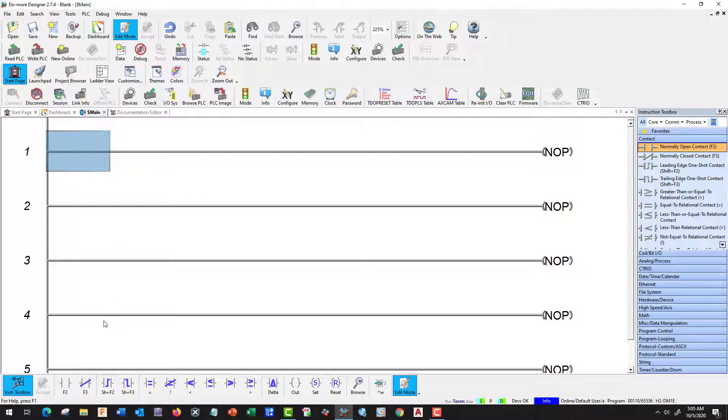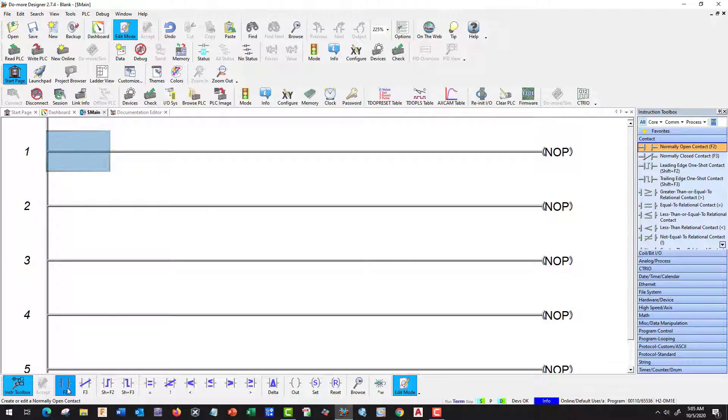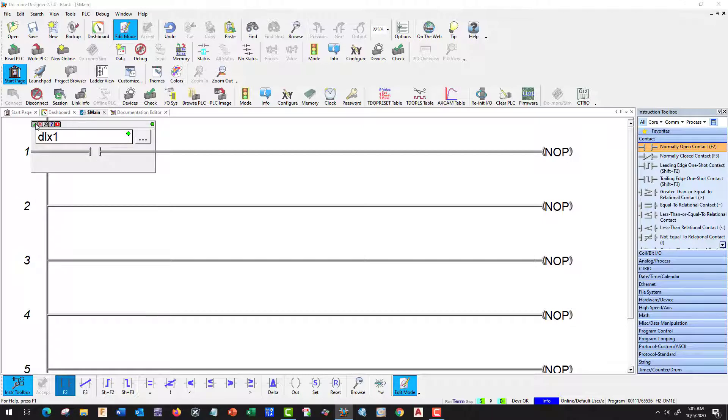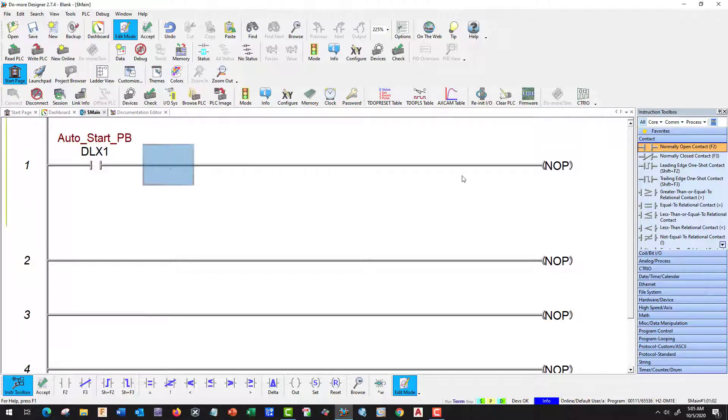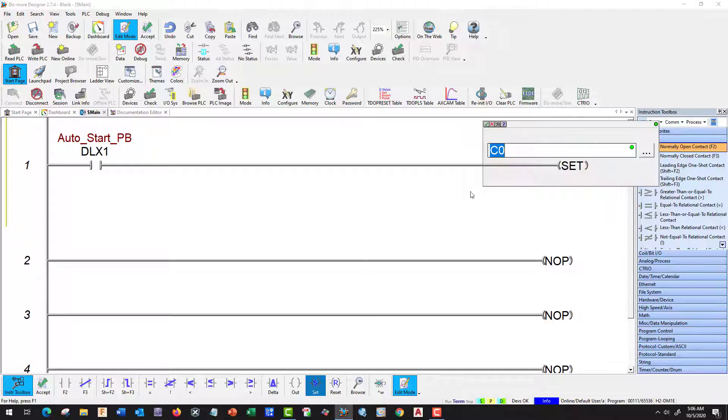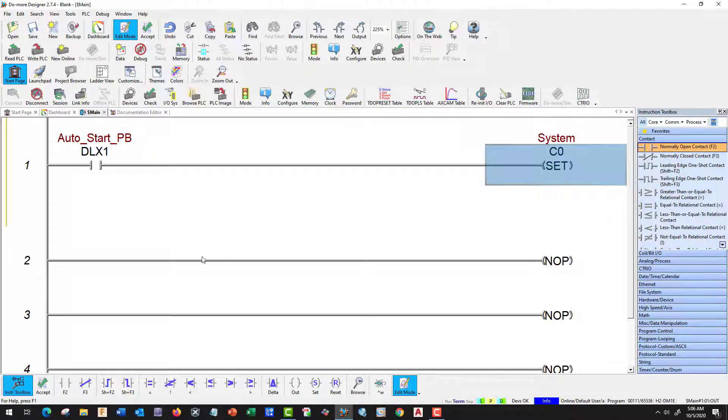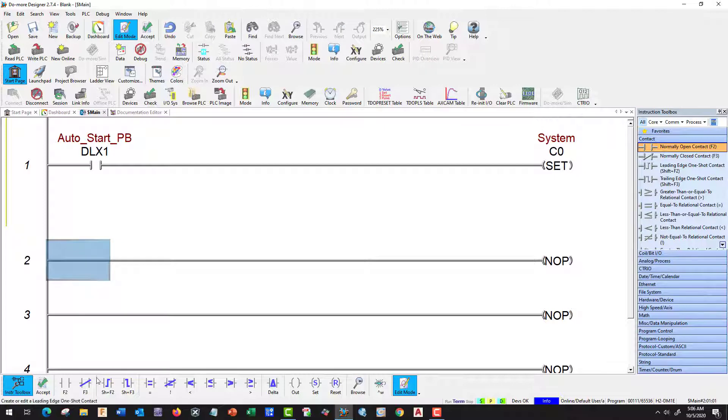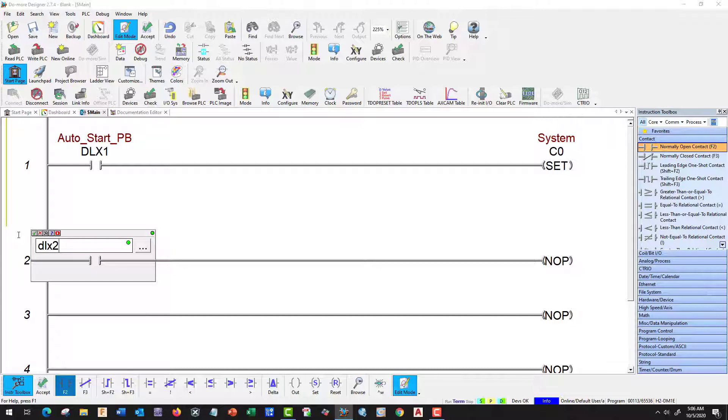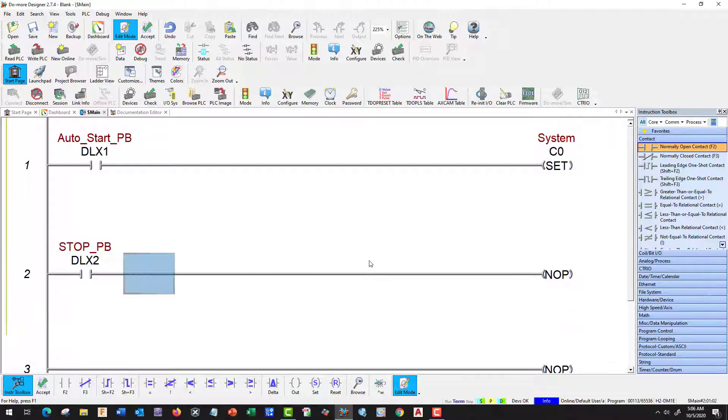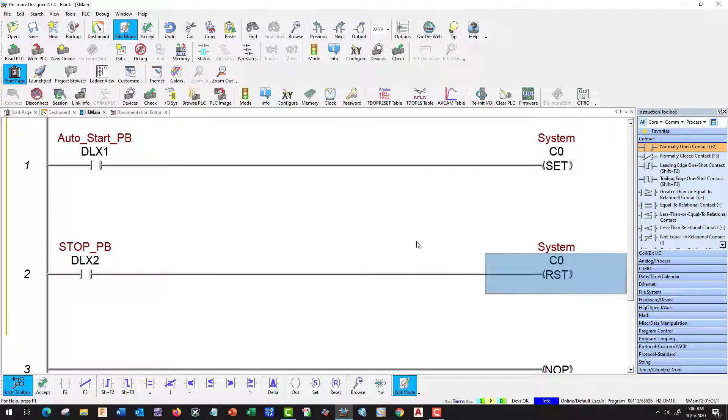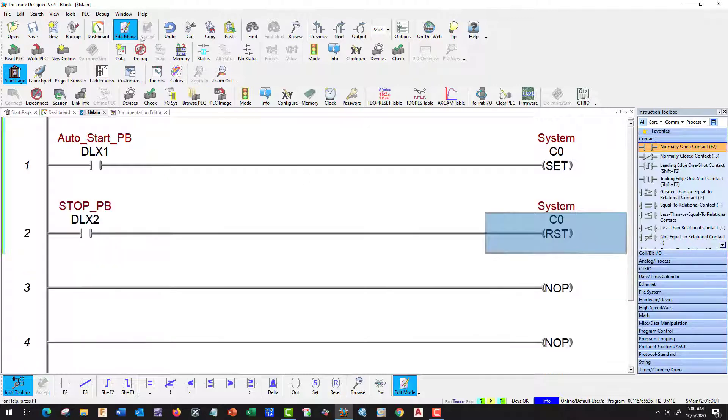We need to do a Start. So let's do a DLX1 which is going to be our Start button and we're going to do a C0 Set. Let's do our Stop which is a DLX2, and we're going to do a Reset for C0. So this will be our Set and Reset. Let's go ahead and accept and save.